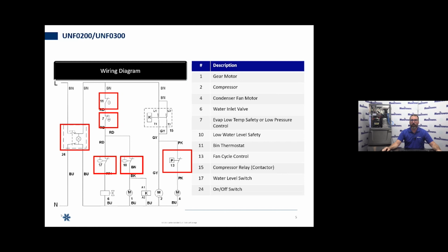Now, on this particular diagram that we have on the screen here, what we're going to want to do is trace our voltage from hot side, which would be brown wire L line, through those switches. And you're going to want to make sure that you have voltage at each point progressing through all of these switches. If we have one open safety, we're definitely going to have a situation where that compressor motor is not going to start up and we're not going to be making ice.